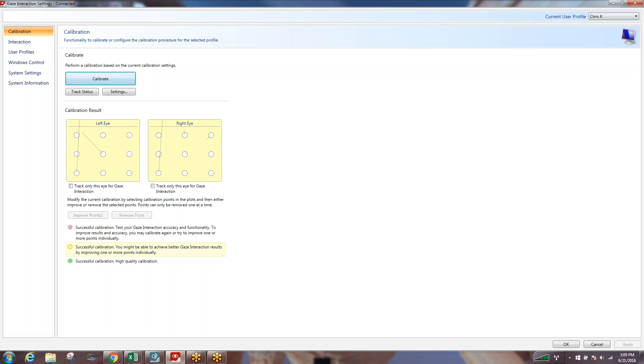Now you'll see that there are a couple of areas of the calibration where I looked away — I didn't get great calibration points. You can see these long lines on the middle one and the lower left-hand corner; everything else I was pretty close. Our goal is to get the natural movement of the eye, or the isolation of the data it's collecting, as close to those white circles as we can. Rather than making the customer go through all nine points again, we can just select those two points and it gives us an 'improve points' option. I'm going to hit improve points and it's only going to bring up those two points.